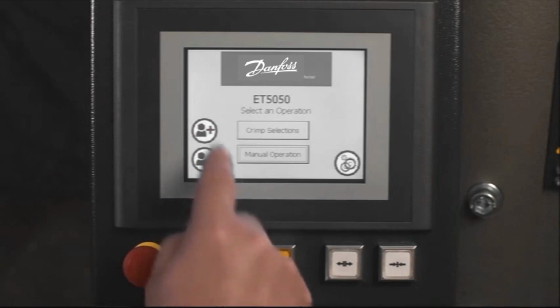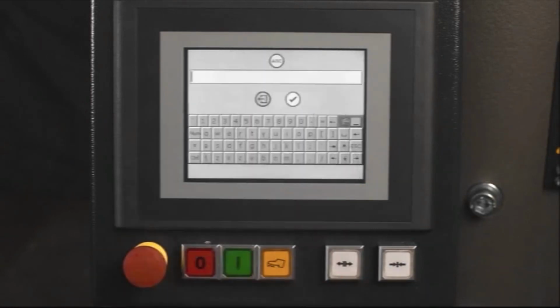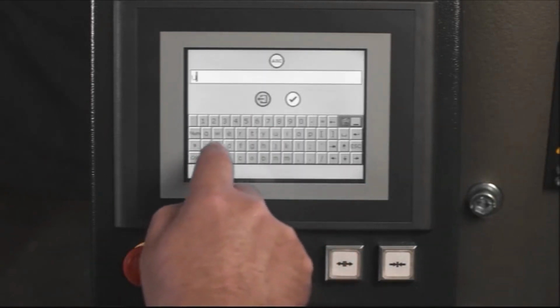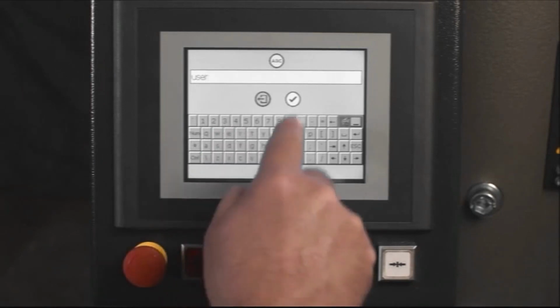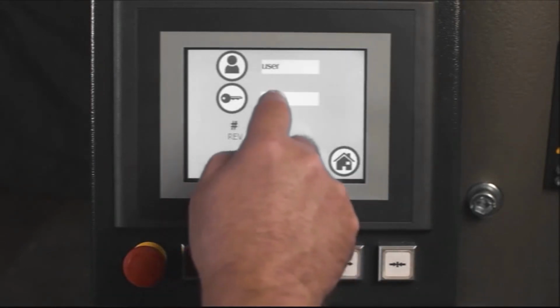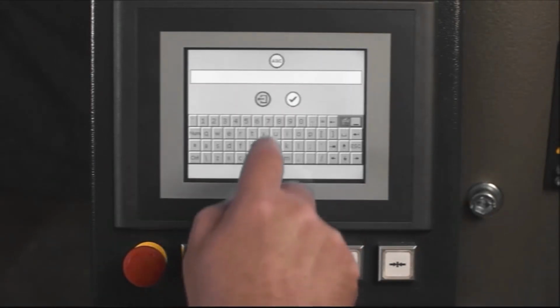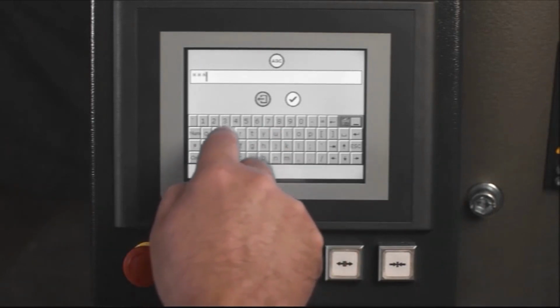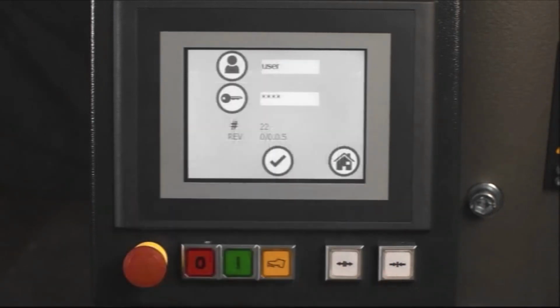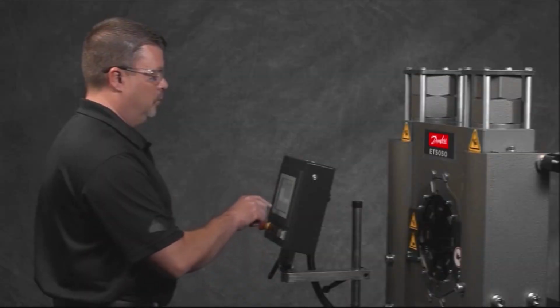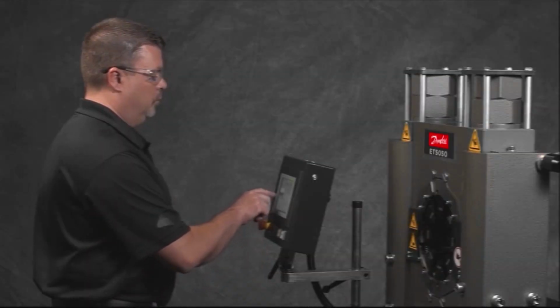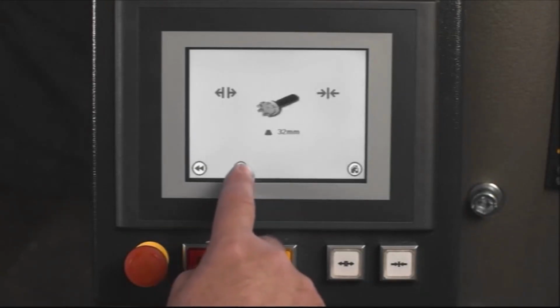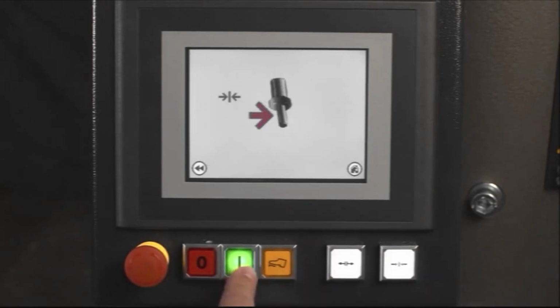After powering on the machine, log in by selecting the user login icon. If users have not been set up on the machine, use the default username and password identified in the operator's manual. After entering the username and password, press the check icon on the screen. Now select the Settings icon and navigate the setting menu using the arrow icon. The calibration option is the 8th menu option.